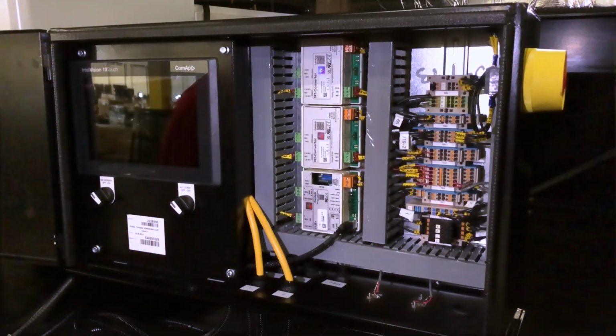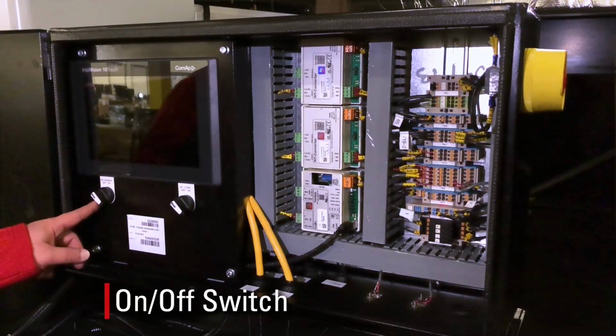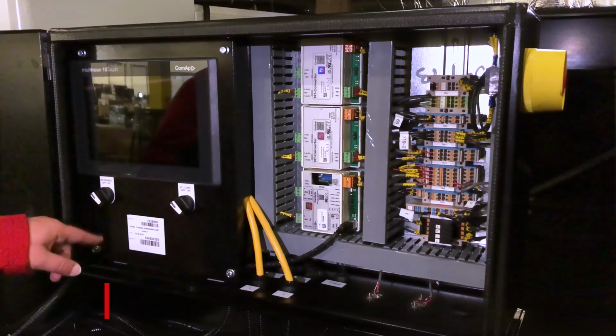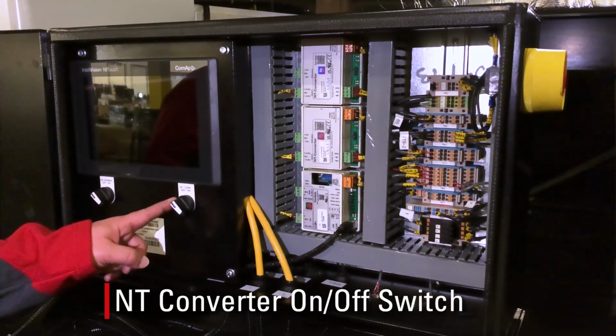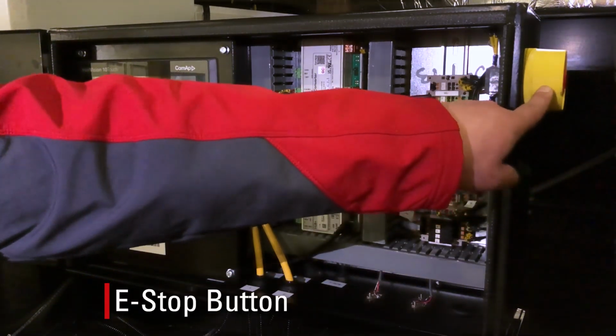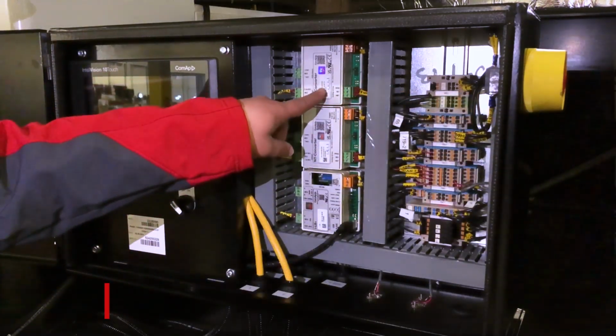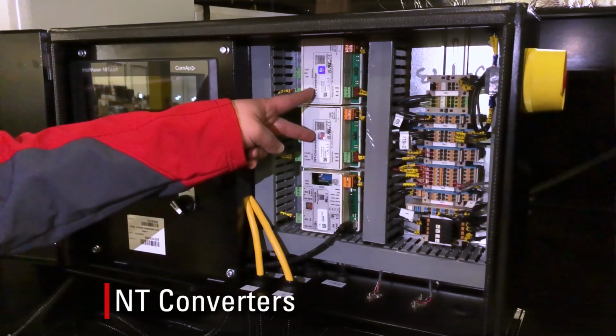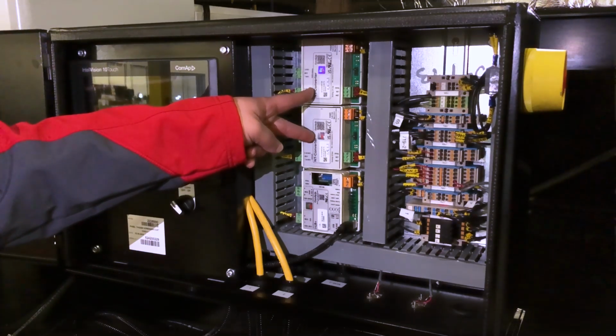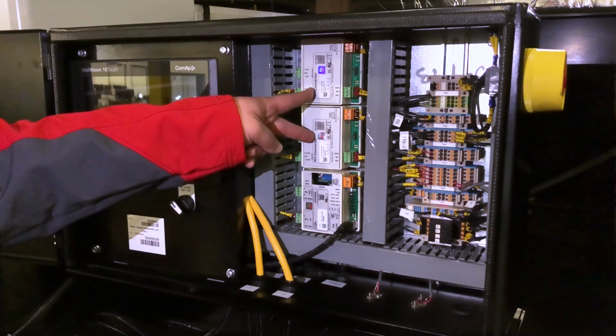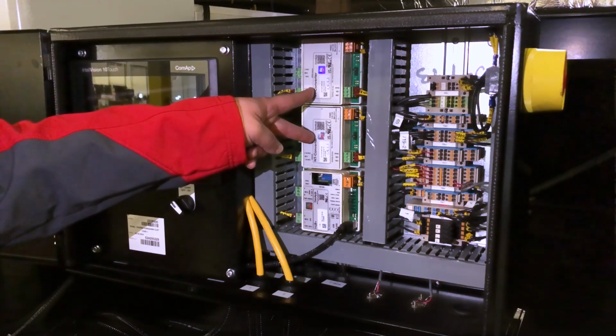Inside the control panel, we have several main features which I'll point out. To begin with, we have our on-off switch for our ComAp InteliVision10 Touch display. We have our NT converter on-off switch, and we have our e-stop, which is located externally. Then we have our NT converters, which are used with analog load sharing with Cummins units. These should remain powered off if you are not load sharing with any Cummins units. If load sharing multiple high power units to Cummins units, please note that you need one pair of NT converters to be powered on, one for kilowatt load share and one for kVAR load share.